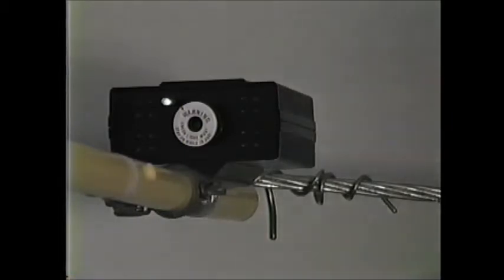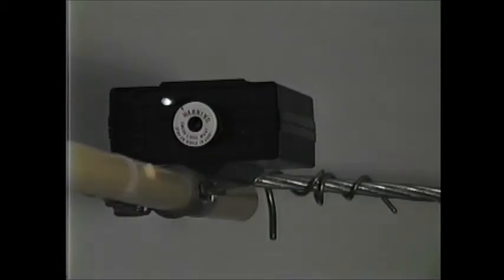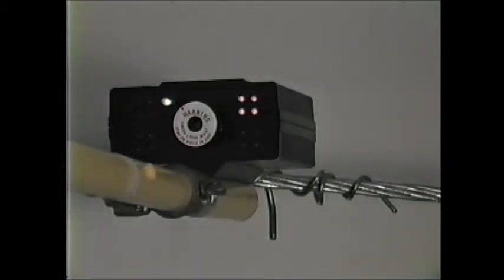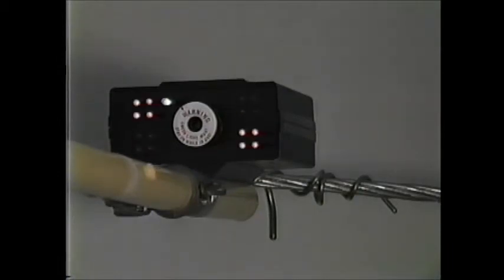If we go in excess of 11,000 volts, which is what we would see on a 34.5 KV system, a 24.9 KV system, or any transmission system that we might be working on, all four banks come on. We know we've got in excess of 11,000 volts and more than likely we have our full system voltage.